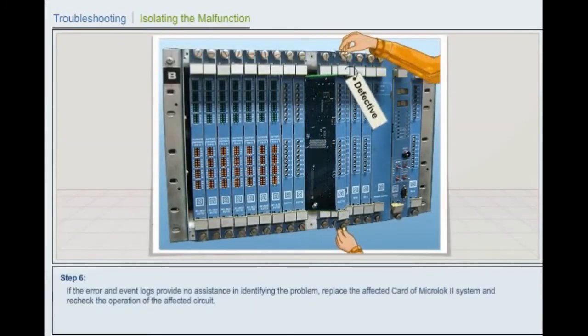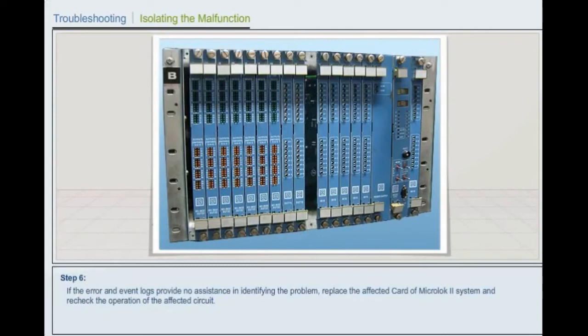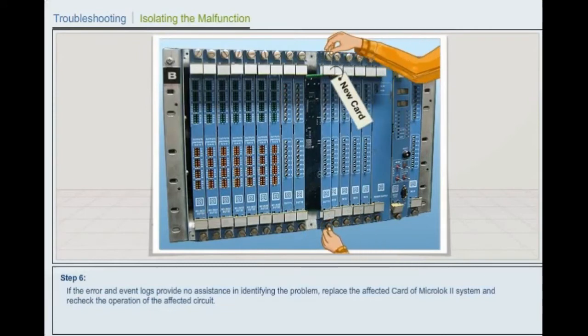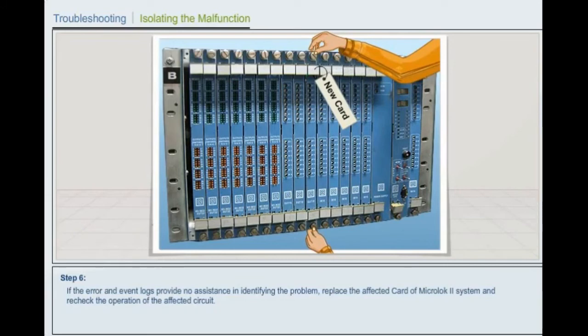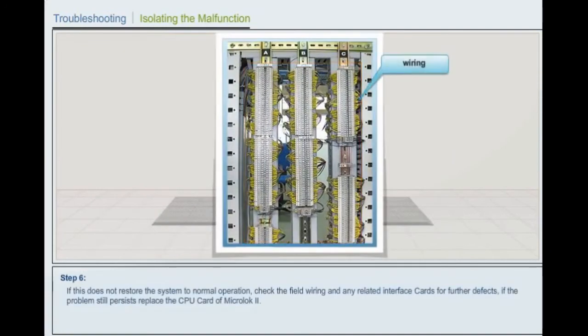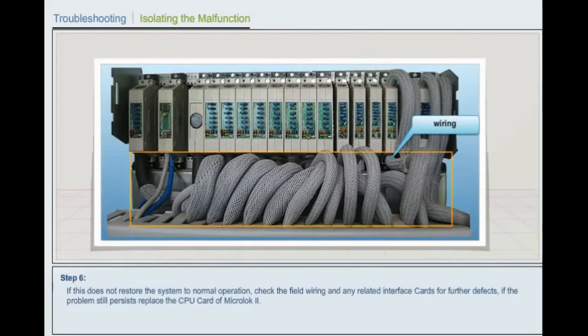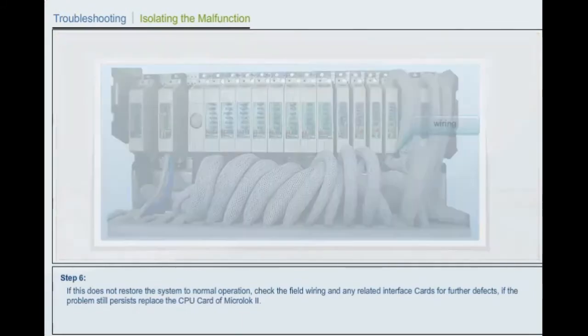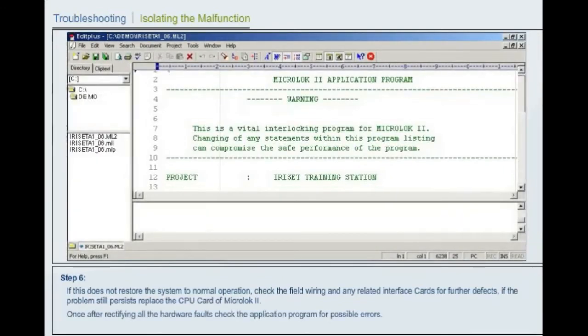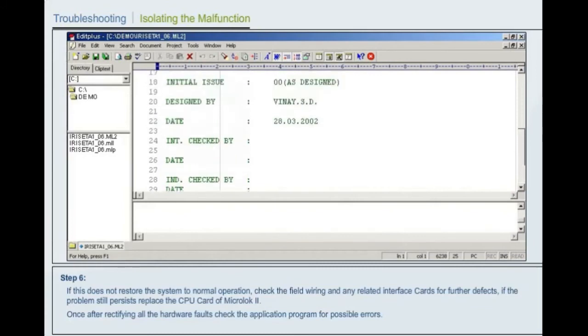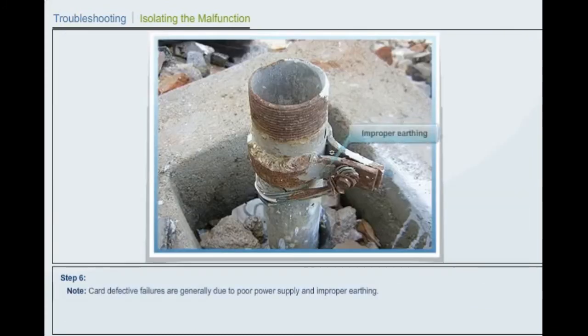Step 6. If the error and event logs provide no assistance in identifying the problem, replace the affected card of the Microlok 2 system and recheck the operation of the affected circuit. If this does not restore the system to normal operation, check the field wiring and any related interface cards for further defects. If the problem still persists, replace the central processing unit card of Microlok 2. Once all the hardware faults are rectified, check the application program for possible errors. Note: card defective failures are generally due to poor power supply and improper earthing.